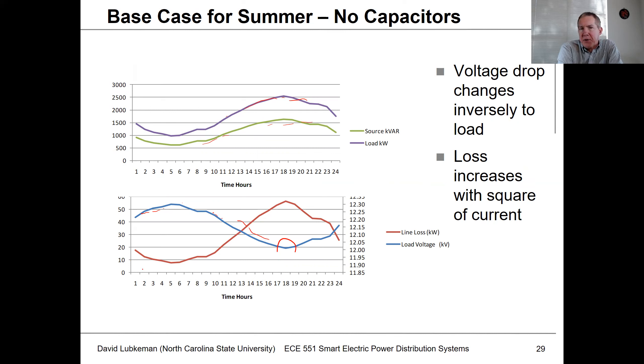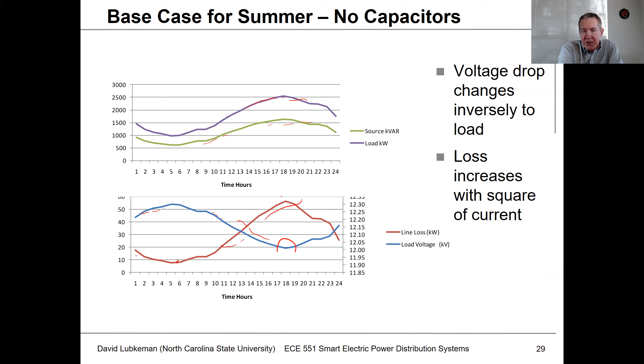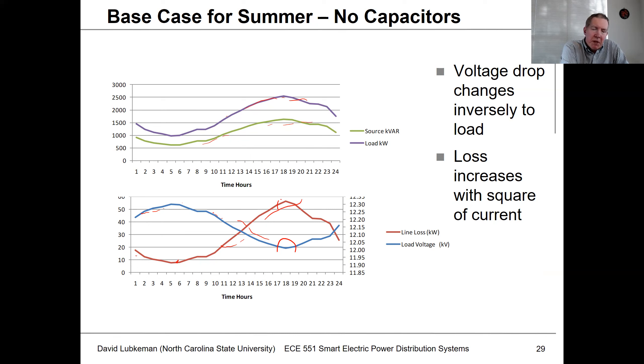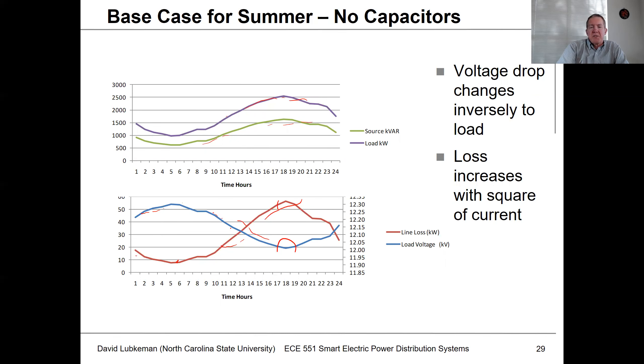Losses have an inverse characteristic. Under light loading conditions, losses are low, but as we approach peak, losses become higher until they're at maximum at peak. Given that losses are related to current squared, it's a quadratic type of relationship. The reality is, if you had a circuit and didn't do anything, you would get a varying voltage across the load, and losses would also vary with time as well.